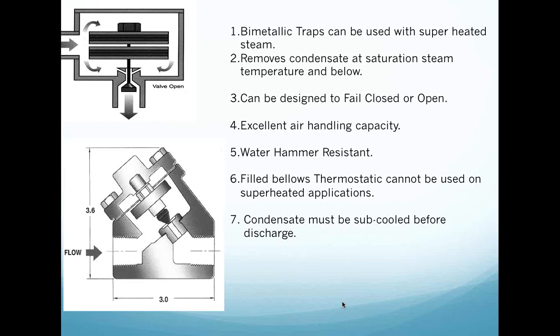If you can imagine these traps in a cool, warming condition where we turn the steam on, but we don't have any heat yet, these will be wide open and they'll be evacuating the air non-condensables that are moving through the system. They are now made in water hammer resistant technologies. 35 years ago, they weren't quite as water hammer resistant. The filled bellows thermostats cannot be used on superheated applications because of that vapor pressure that I had discussed with you. And then condensate must be subcooled, which is the most important item that I would like you to remember for this technology.